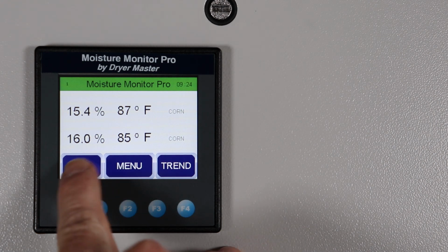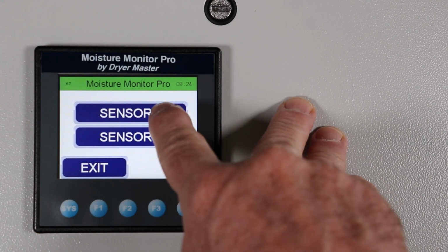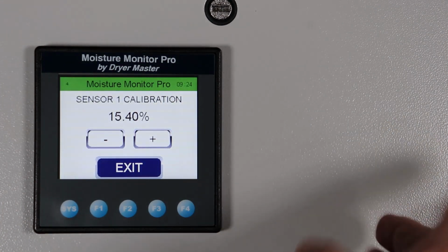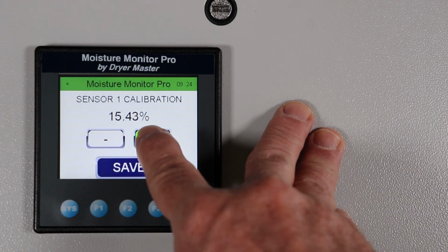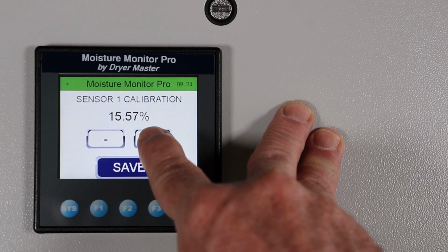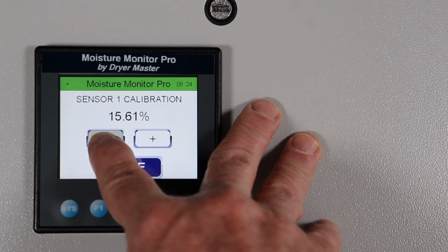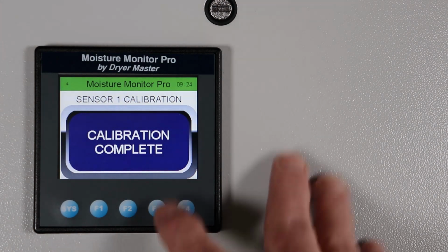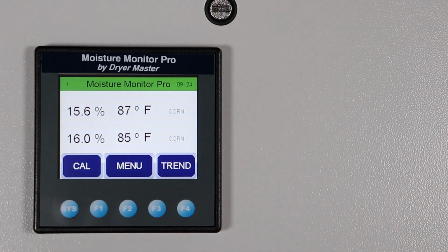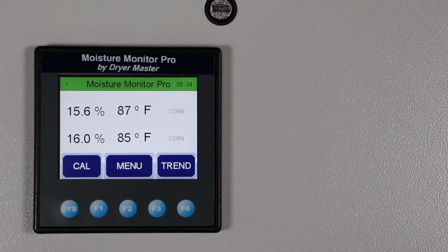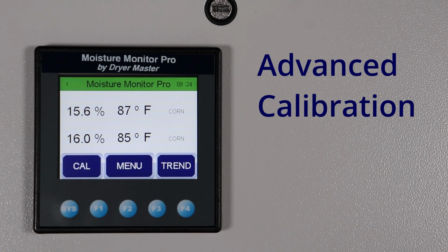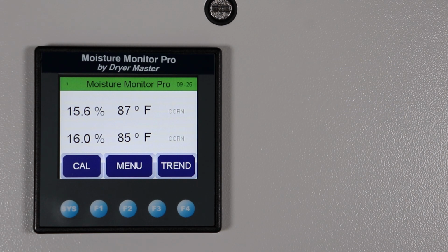And you want to adjust the dryer master to read 15.6. So what we would do is you hit the calibration screen. We pick sensor 1 and there's 15.4. We just do it like this. Now we're at 15.6. We go save, calibration complete, and now the dryer master reads 15.6. So that's a very quick way of doing a calibration. The other way is what we call the advanced way, and you may use a calibration button, or we can use a virtual calibration button from the screen, which is what I'm going to show you next.